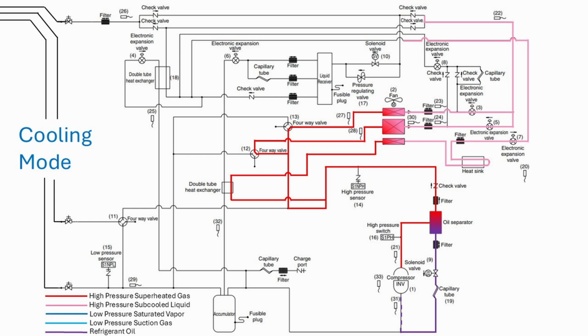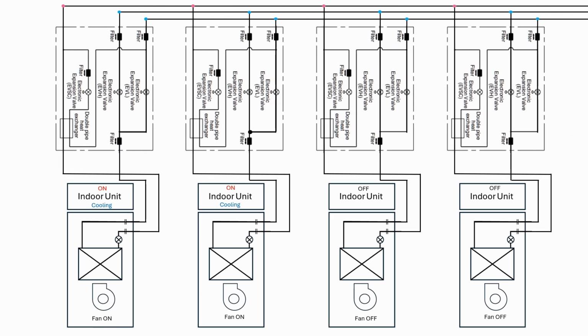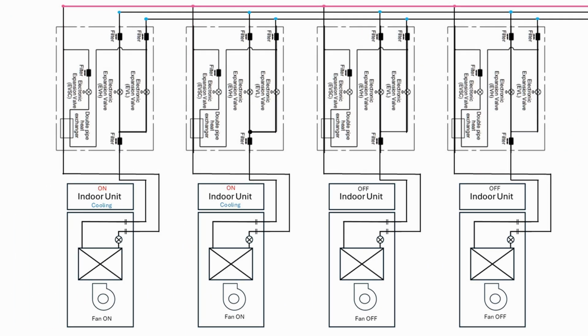The 2 larger sections of outdoor heat exchanger are piped through a solenoid valve and into a liquid receiver. The liquid refrigerant leaving the receiver then meets up with the refrigerant from the 3rd section of heat exchanger. It's all then directed indoors to be distributed to the indoor units. The liquid refrigerant travels from the outdoor unit to the indoors on the small liquid line. The line is connected directly to the branch selector box.